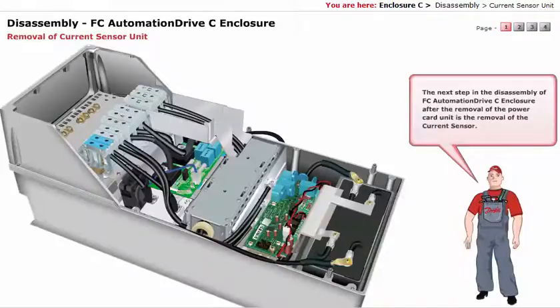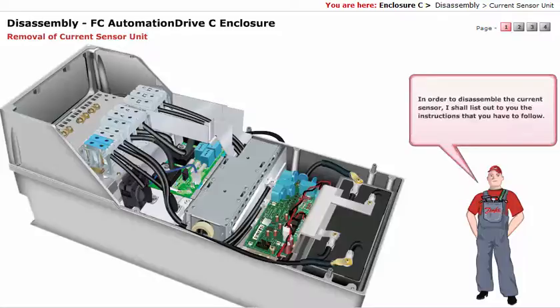The next step in the disassembly of FC AutomationDrive C Enclosure, after the removal of the power card unit, is the removal of the current sensor. In order to disassemble the current sensor, first you have to loosen the screws of the input line cables L1, L2, L3 as indicated using the Allen keys, and remove the input line cables.